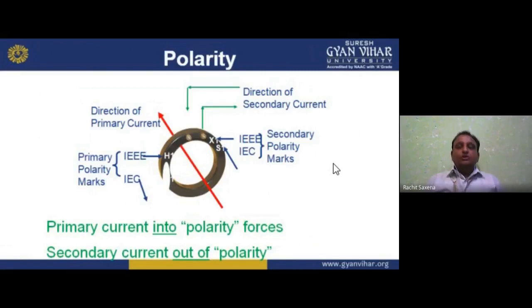Polarity. If I want to identify the polarity, my dear students, it will be given like this. The direction of current is always shown like this arrow. The direction of the secondary current is this. This is the secondary point, and this is the primary point. The Institute of Electrical and Electronics Engineers, that is IEEE, and IEC give the secondary polarity marks, that is X1. So as per IEEE and IEC, we always use X1 for the secondary. Basically it would be S1 for secondary, but we have to follow the polarity marks given by IEEE and IEC. They are the governing body, or we can say the statutory body, which tells how we follow things in electrical and electronics engineering. They make X1 for the secondary and H1 for the primary. So the primary polarity mark given by IEEE and IEC is H1, and X1 is for the secondary side. So that is the secondary polarity mark.